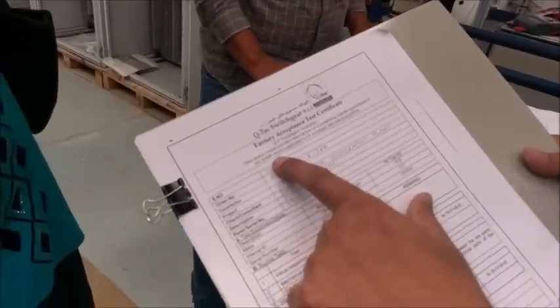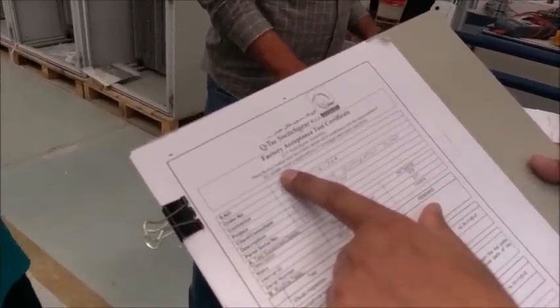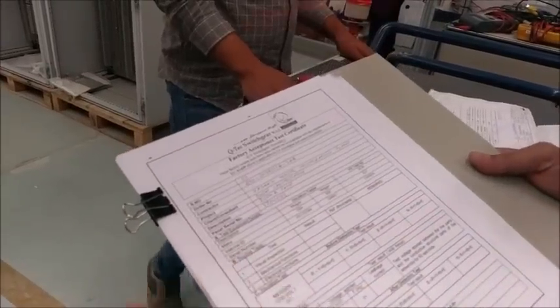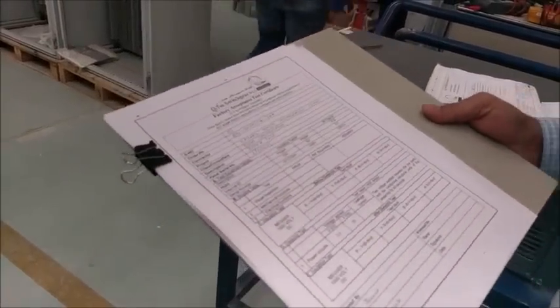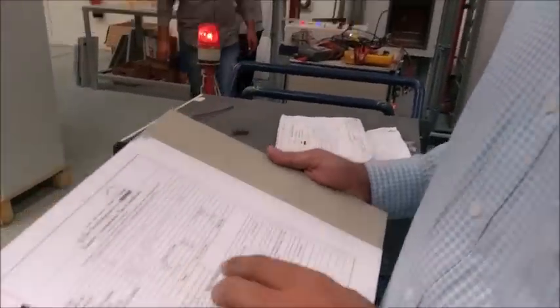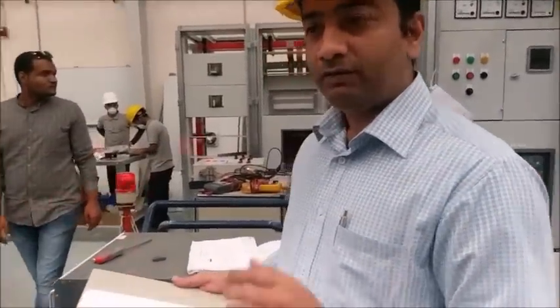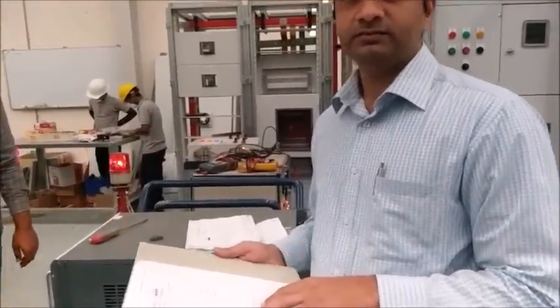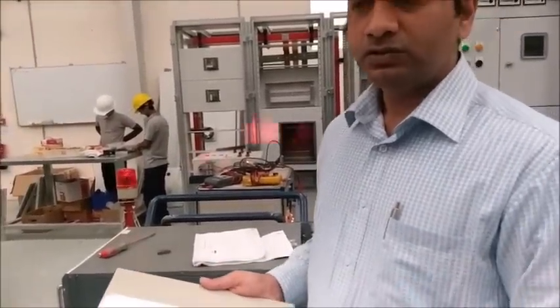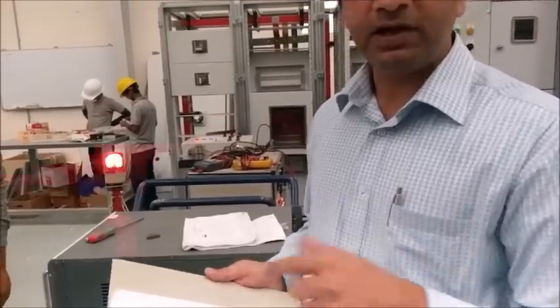We have, as per IEC 61439, a standard test which is to be followed for each and every panel. Now what we have done is, whenever the customer is here, they want to witness the test. So we are testing in front of them.